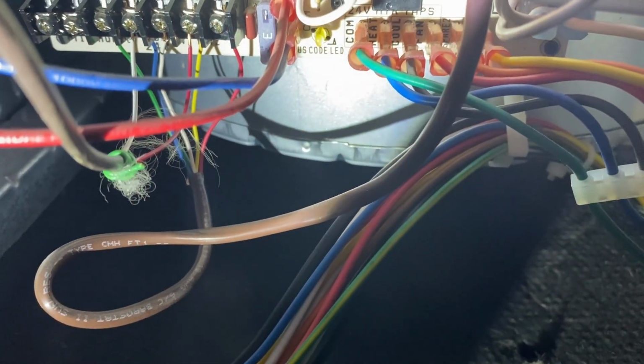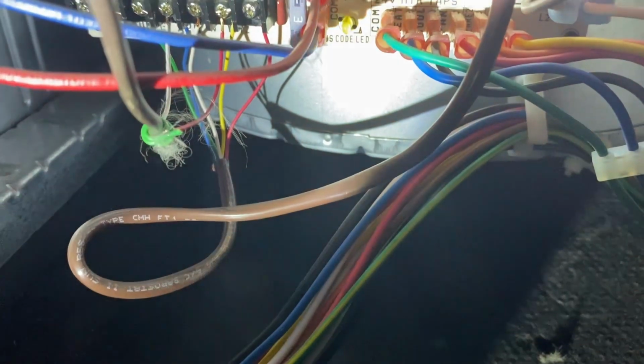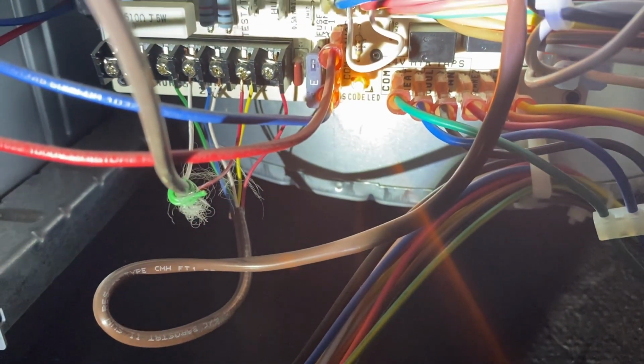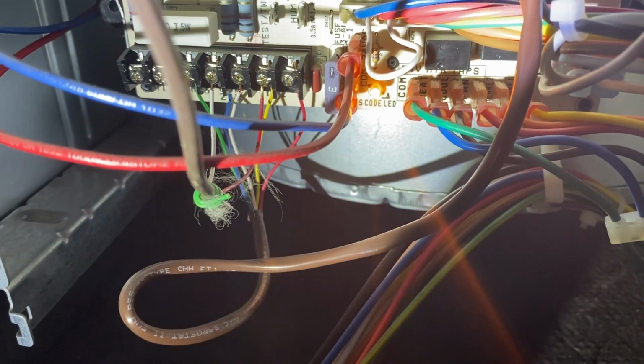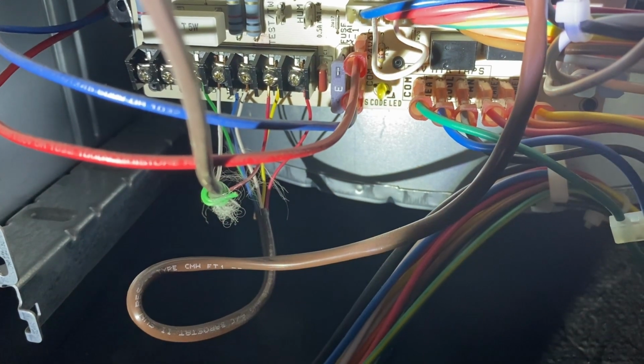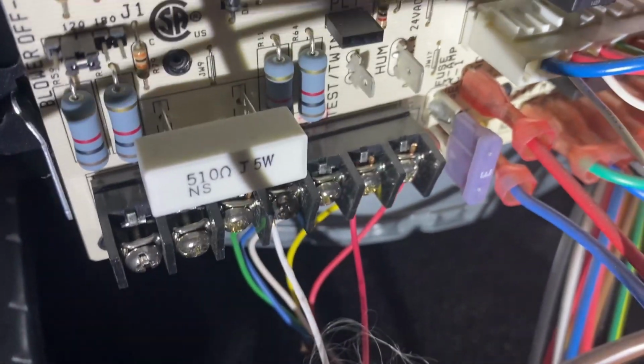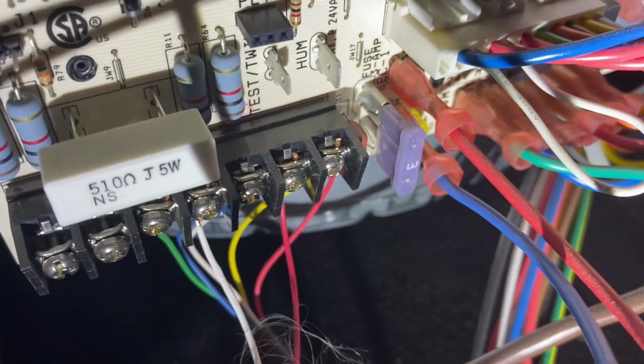Check the indicator light. It's flashing two short and four long. You may look up the instruction manual to check what this indicator pattern means. For this particular Carrier brand HVAC, the two short and four long flashing signal means blown fuse. Switch off the door switch and remove the fuse.